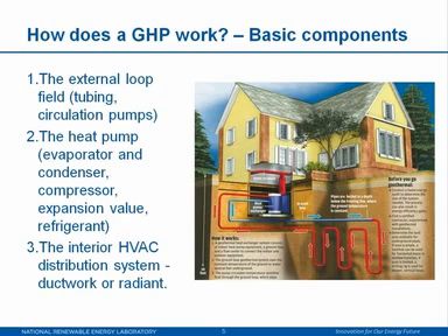And then you have the interior HVAC distribution system. How are you getting the heating and cooling distributed through the house? These systems can use either ductwork or radiant floor. Often, if it's a radiant system, your ground source heat pump system would only provide heating. It wouldn't provide cooling. If it's a ductwork system, where you're basically replacing the forced air furnace and the AC unit, it would provide both heating and cooling. Essentially, the ground source heat pump system is not terribly different from an air source heat pump unit, which are much more common, except that you're using the ground as the place where you're deriving your heat or dumping your heat.